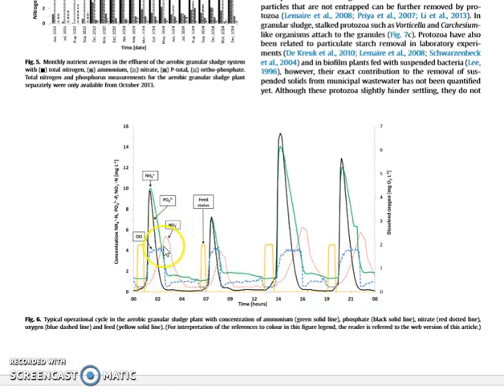We also see nitrate going up initially when aeration is going on, as ammonia is transferred into nitrate. Then when aeration is turned off and oxygen level drops, nitrate also drops due to denitrification, and then the cycle starts over. Each cycle is somewhat different during the 24-hour period, with much larger peaks during the day when there is more concentrated sewer flow, while during the night concentrations and amounts are lower.